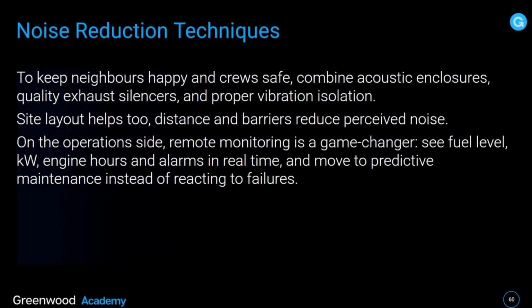Now, to keep neighbours happy and crews safe, combine acoustic enclosures, quality exhaust silencers, and proper vibration isolation. Site layout helps too. Distance and barriers reduce perceived noise. On the operations side, remote monitoring is a game changer. See fuel level, kilowatt, engine hours and alarms in real time and move to predictive maintenance instead of reacting to failures.